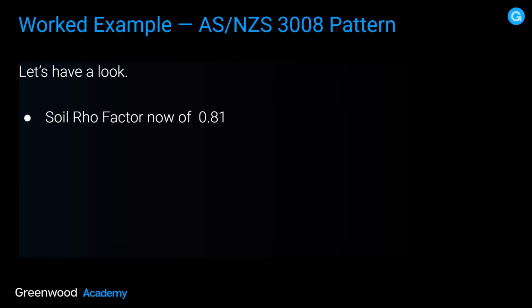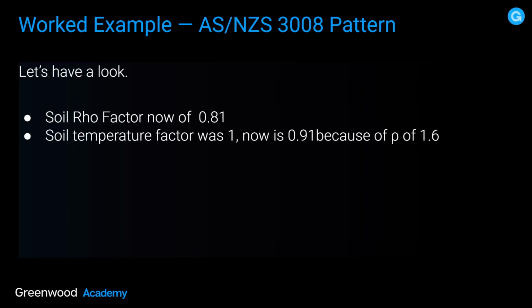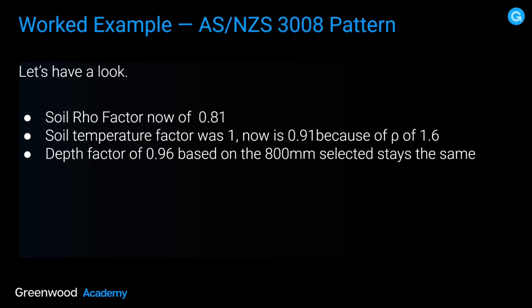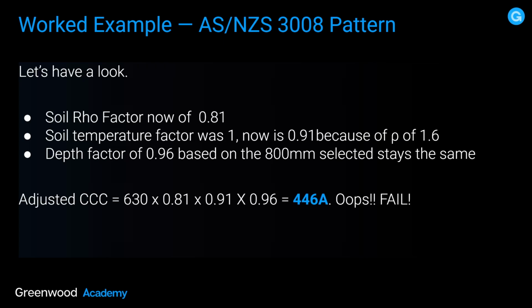Let's have a look. So we've got a soil factor now of 0.81. Okay. We got a soil temperature factor. It was 1, now it's 0.91, and that's because of the thermal resistivity of 1.6. The depth factor of 0.96 based on the 800mm selected stays the same because we haven't changed the depth of bury. So the adjusted current carrying capacity is now 630 amps times 0.81 times 0.91 times 0.96, and it equals 446 amps. Uh-oh, that's a fail. So we've effectively failed. The question is, can we vary any of these?